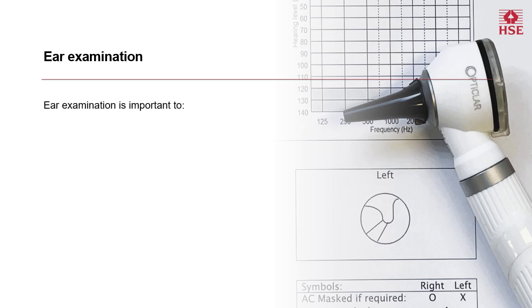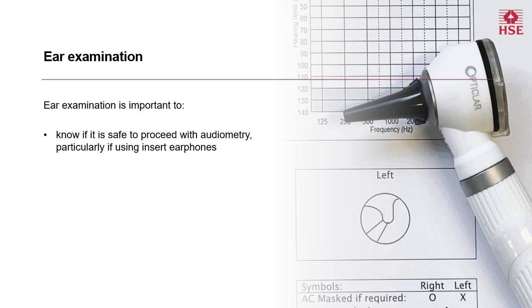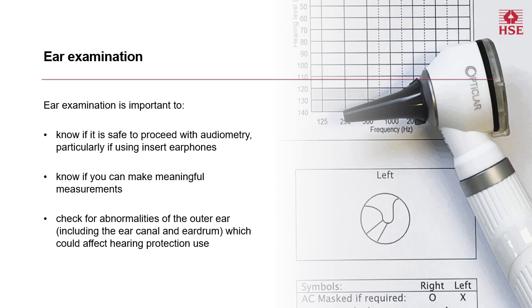Ear examination is important to know if it is safe to proceed with audiometry, particularly if using insert earphones, and to know if you can make meaningful measurements. Again, this is especially important to ensure that your baseline measurement is valid. It is also important to check for abnormalities of the outer ear, including the ear canal and eardrum, which could affect hearing protection use.